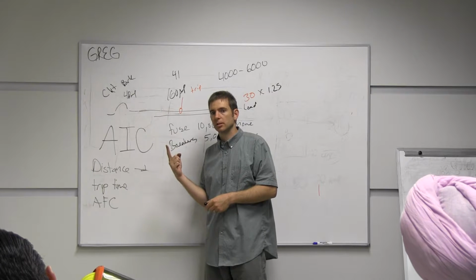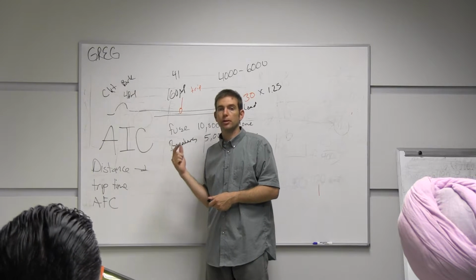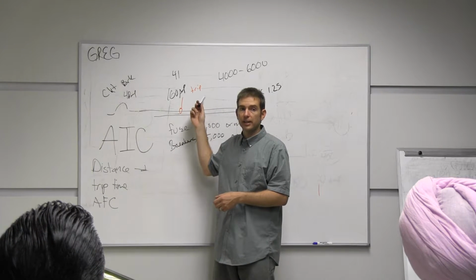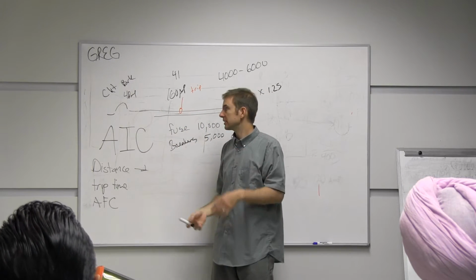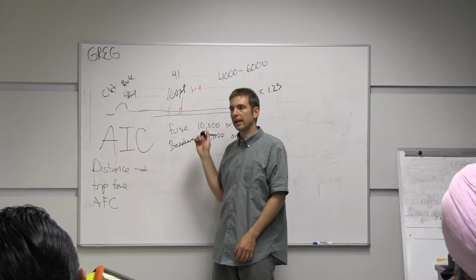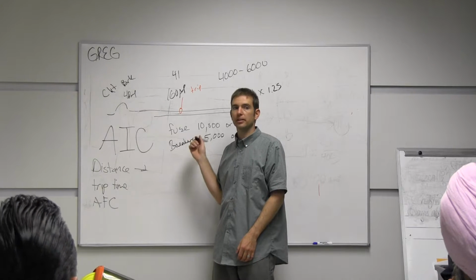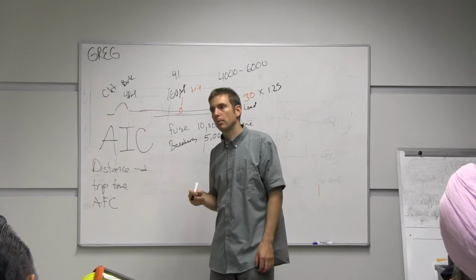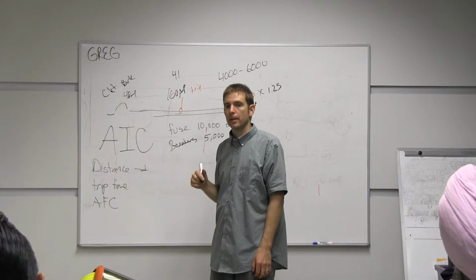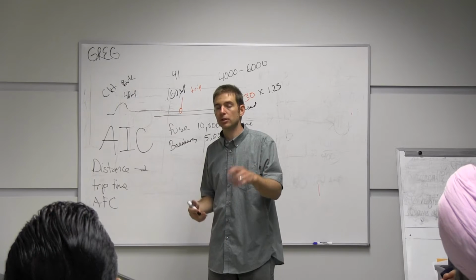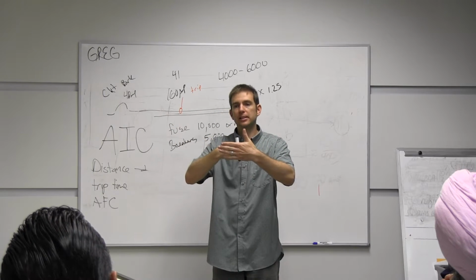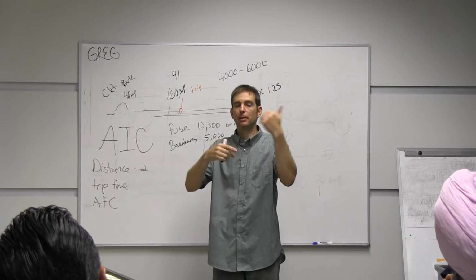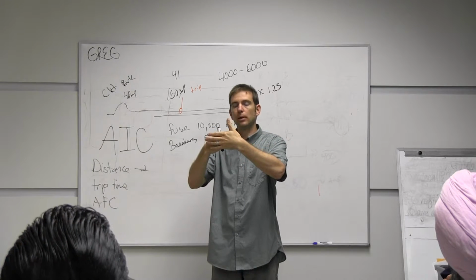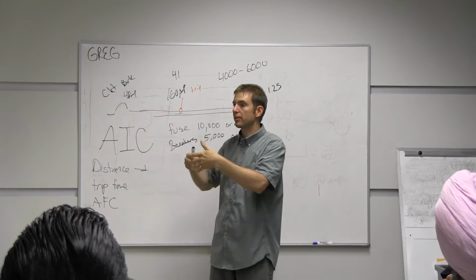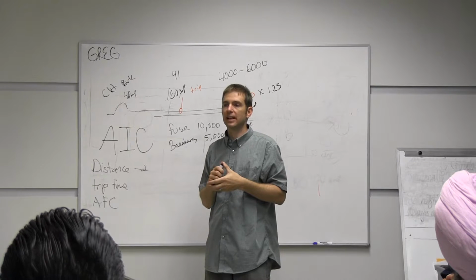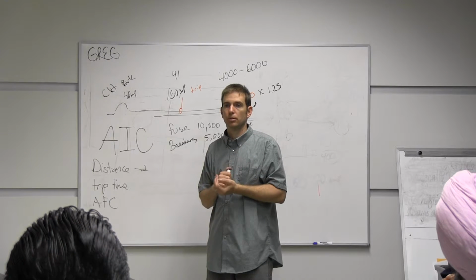Well, is it the same voltage? Some panels are 600 volts. Some panels are 250 volts. Some panels are 100,000 amps interrupting capacity. They're rated for that. Some are 10,000. You put a 10,000 AIC rated panel where a 100,000 amp rated panel was, then let's say you have a fault condition. Someone goes over there, well, I have a tripped circuit breaker. You go to flip it back. Well, now you're making contact on that fault right in front of you. So that arc, instead of being down the line, it's right in your face. So you might have 80,000 amps traveling through that circuit breaker that's only capable of 10,000 amps. That could explode. So that's not safe.